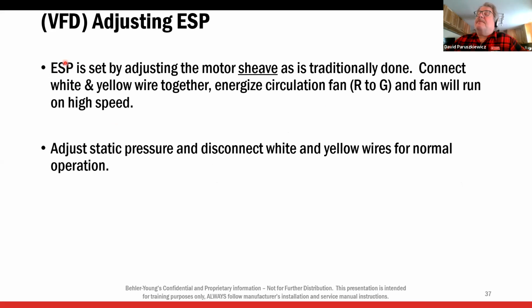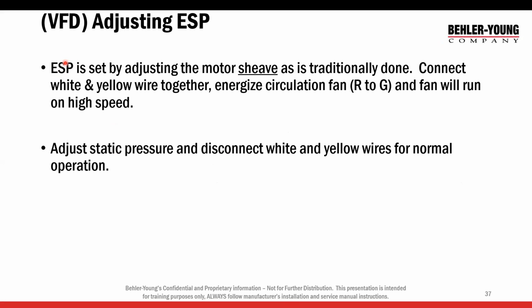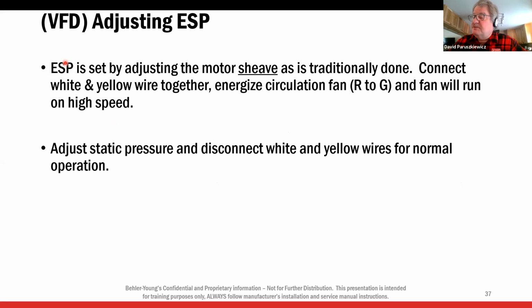All right. Air balancer. Yeah. Quick question. For the VFD, what AC voltage powers it? Whatever the unit is, either 230 or 460. It depends on whatever the unit is. So if it's a 230 volt unit, we have 230 going to the VFD. All right. If it's a 460 unit, we have 460 going to the VFD.